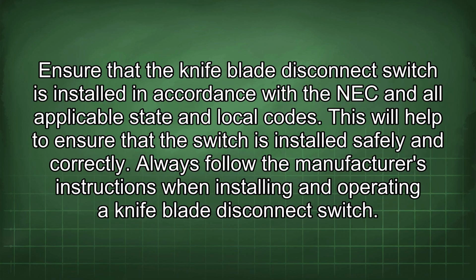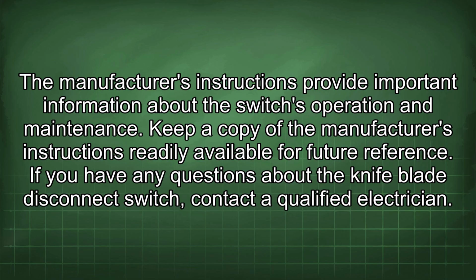Ensure that the knife blade disconnect switch is installed in accordance with the NEC and all applicable state and local codes. This will help to ensure that the switch is installed safely and correctly. Always follow the manufacturer's instructions when installing and operating a knife blade disconnect switch. The manufacturer's instructions provide important information about the switch's operation and maintenance. Keep a copy of the manufacturer's instructions readily available for future reference. If you have any questions about the knife blade disconnect switch, contact a qualified electrician.